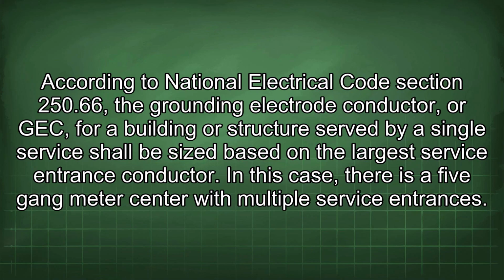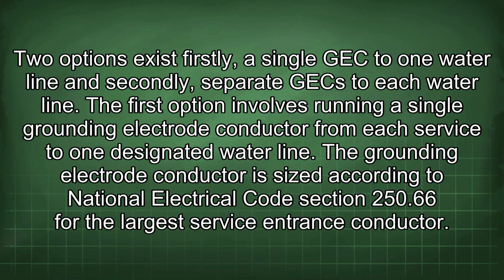According to National Electrical Code Section 250.66, the grounding electrode conductor, or GEC, for a building or structure served by a single service shall be sized based on the largest service entrance conductor. In this case, there is a 5-gang meter center with multiple service entrances. Two options exist: firstly, a single GEC to one water line, and secondly, separate GEC to each water line.